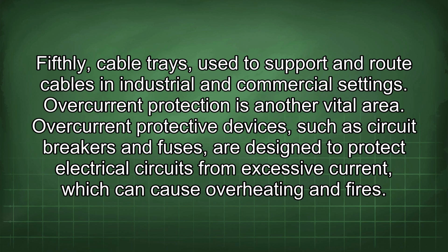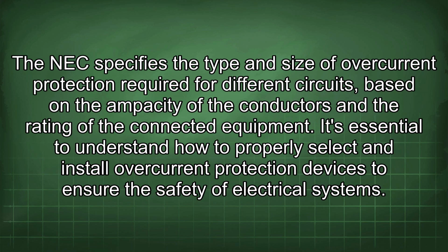Overcurrent protection is another vital area. Overcurrent protective devices, such as circuit breakers and fuses, are designed to protect electrical circuits from excessive current, which can cause overheating and fires. The NEC specifies the type and size of overcurrent protection required for different circuits, based on the ampacity of the conductors and the rating of the connected equipment. It's essential to understand how to properly select and install overcurrent protection devices to ensure the safety of electrical systems.